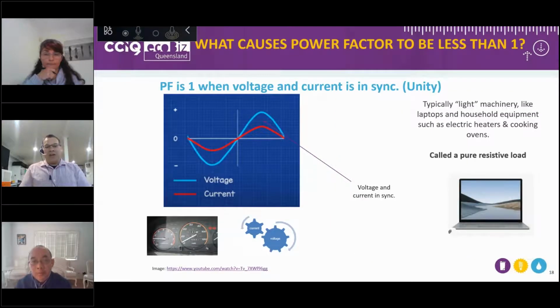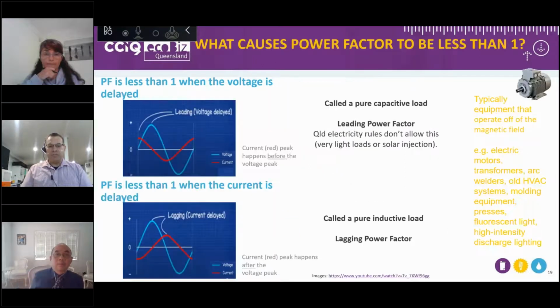Okay, so to get a little bit more mathematical, power factor is 1 when the voltage and the current are in sync. You can see on the graph the blue line and the red line are syncing, as in unity, and therefore your power factor is 1. Then you have your two scenarios, when your current lags or leads the voltage. That is referred to as leading or lagging power factor.